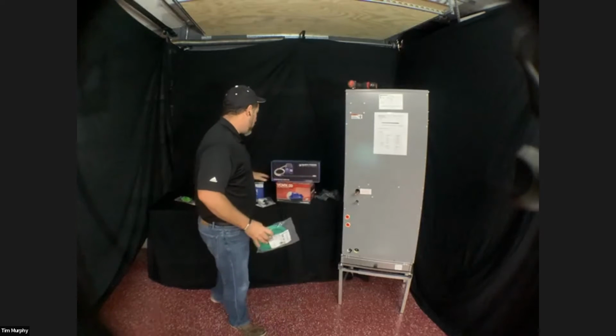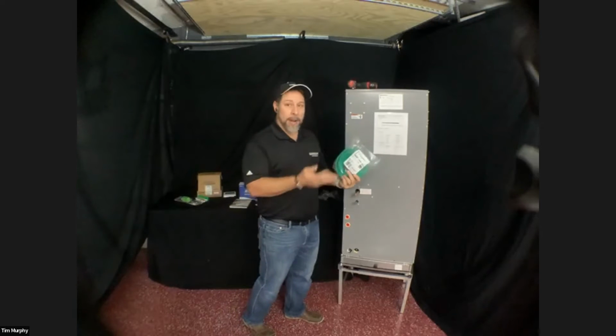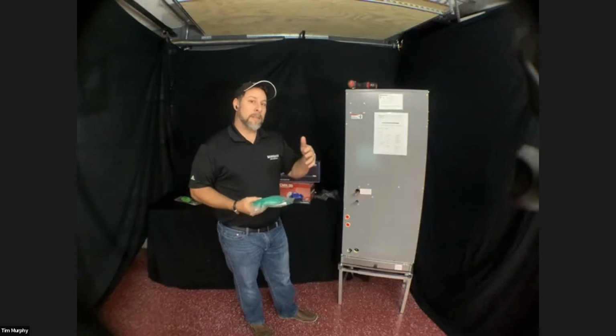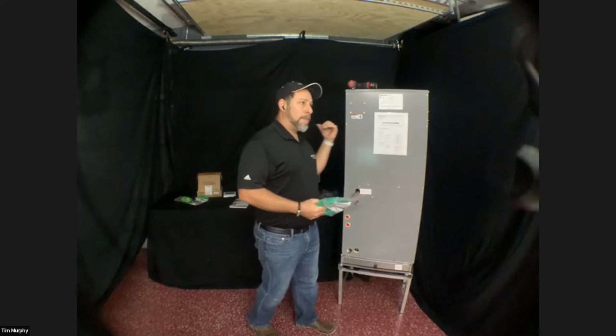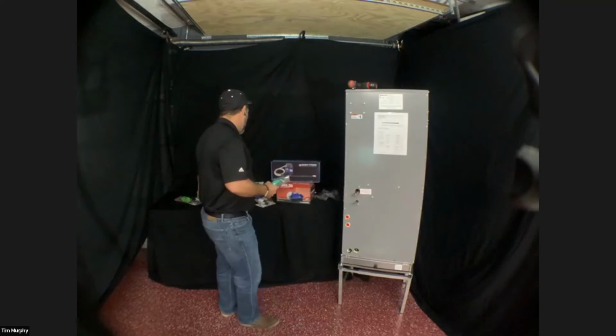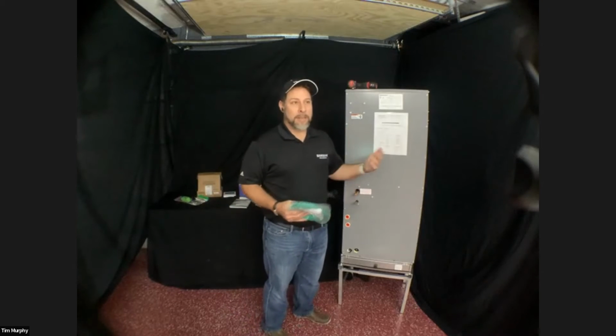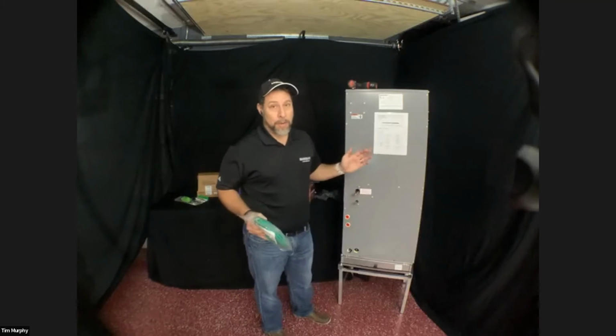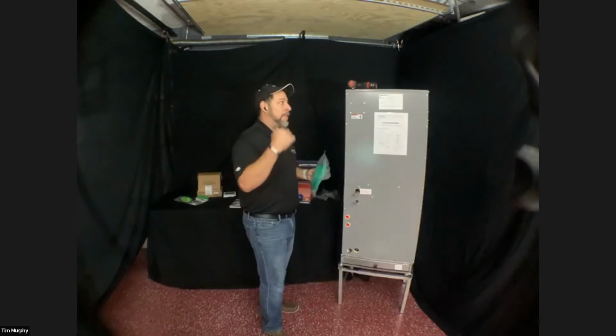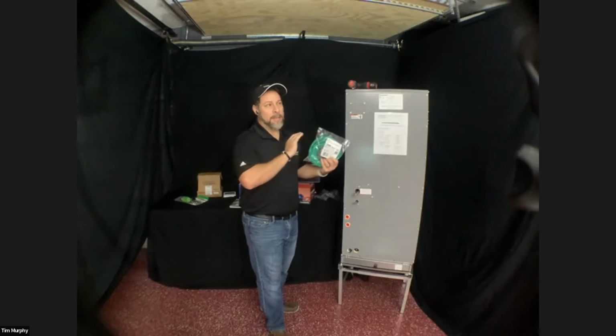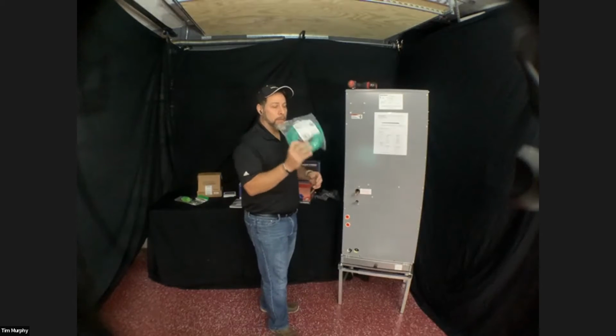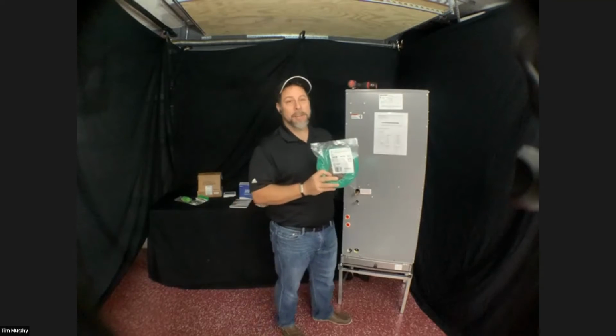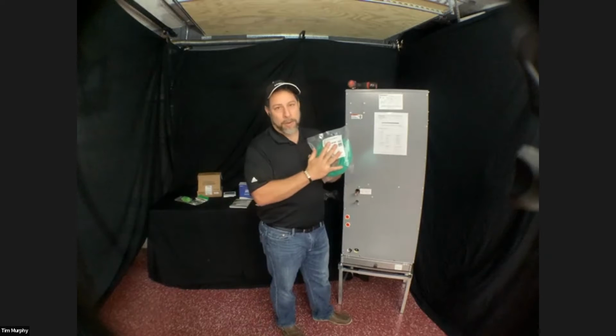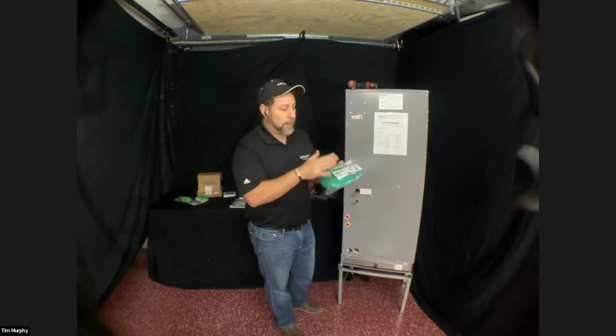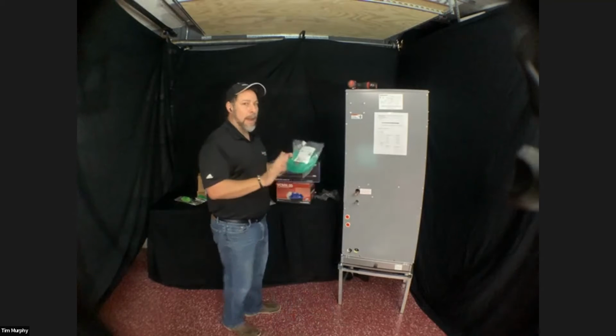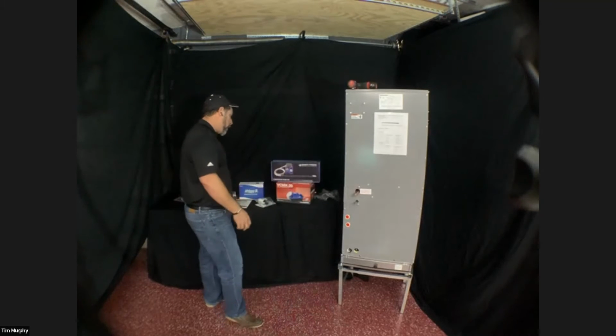Also, running this to the advanced controller is something I recommend as well. I have talked to some of the guys at Samsung, and they said that if you have a regular thermostat wire, only to the advanced wire controller, is something they've seen done and have had success with no issues. I look at it as, if you're installing it, just use this. It's not worth having a callback over something because we didn't run the 16-2 stranded shielded wire. So I really recommend that you always run this. We sell it. It's very affordable, and you just buy it, put it in, and that way you don't have to worry about having communication errors later on in the future.